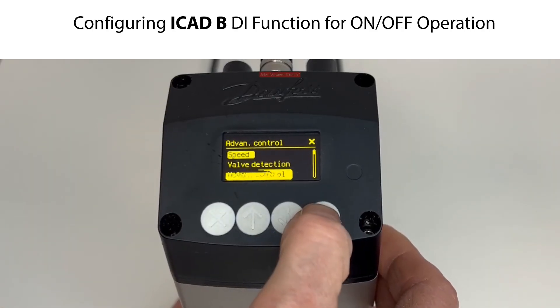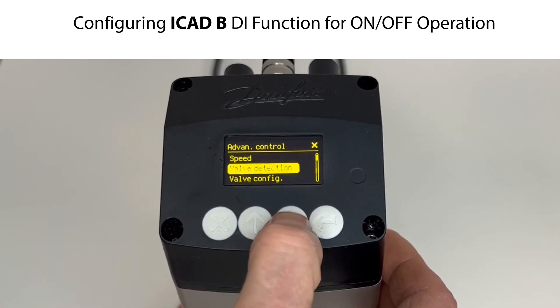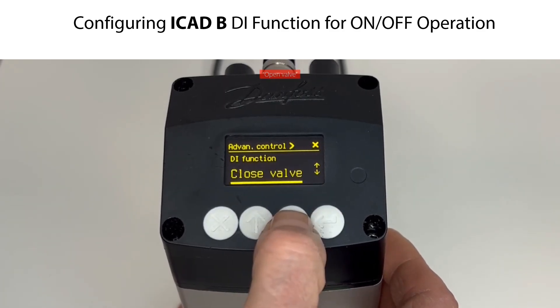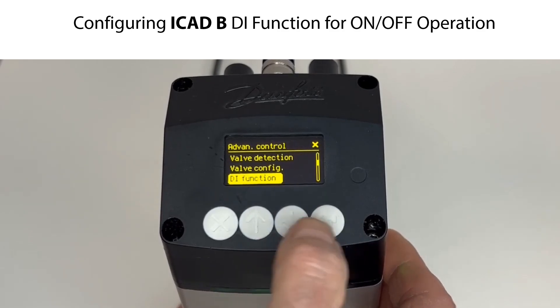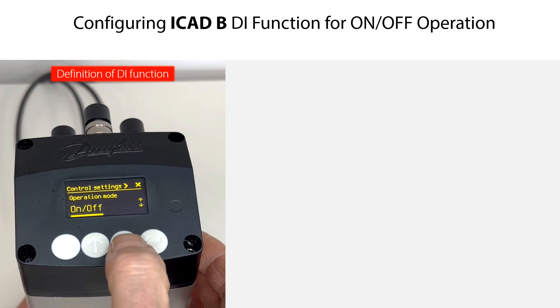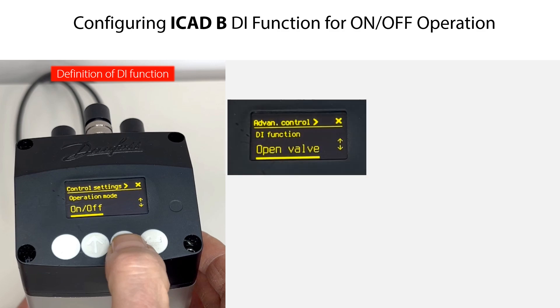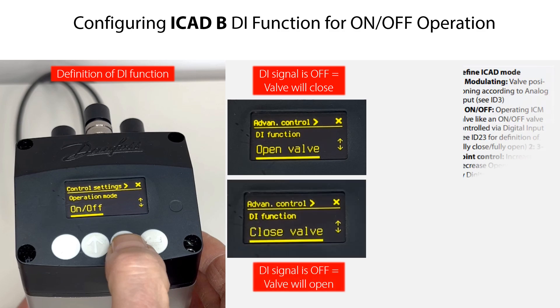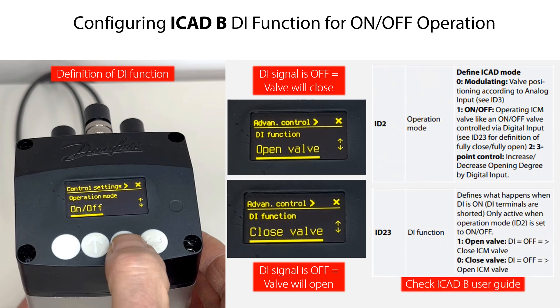Scroll down to Advanced Control, then press Enter. Scroll down to DI Function, then press Enter. Select between Open Valve and Close Valve. Press Enter to confirm the needed function, then press Exit several times to return to Service. Please note that if selecting Open Valve, this will close the valve when the DI signal is off. And if selecting Close Valve, this will open the valve when the DI signal is off. You can find more information about the DI Function in the ICAD-B User Guide, as illustrated here.